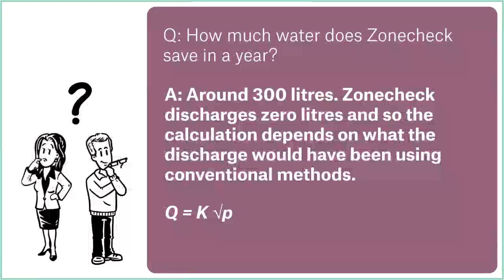And in order to work that out, obviously it involves a calculation, and it involves some figures which we don't necessarily know. So first of all, we need to know how long you are discharging water for. How long is the valve in the open position? Obviously that will depend on the time delay on the flow switch. The flow switches have got a time delay. In the UK, it's 0 to 30 seconds. In other countries, it could be up to 60 seconds.